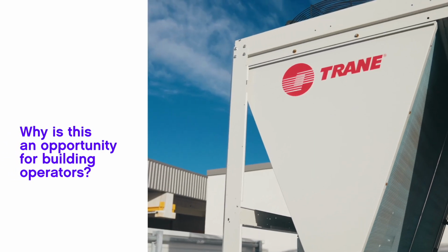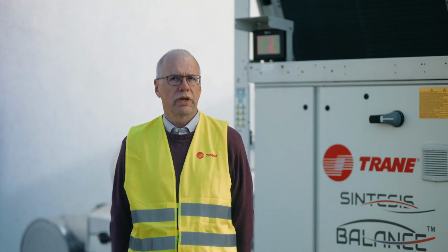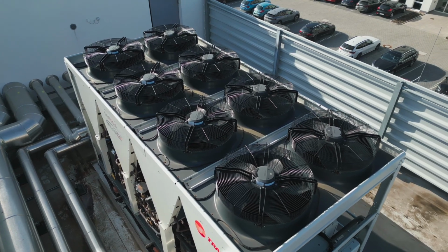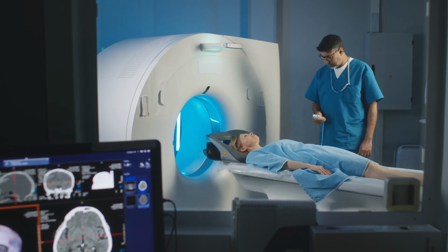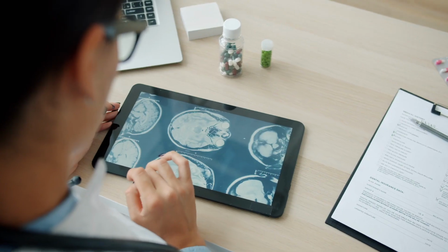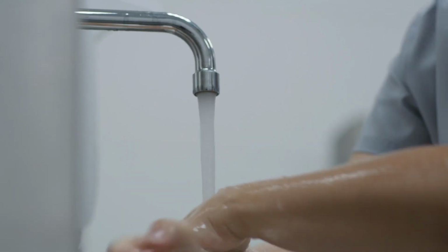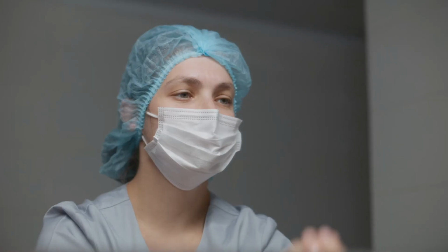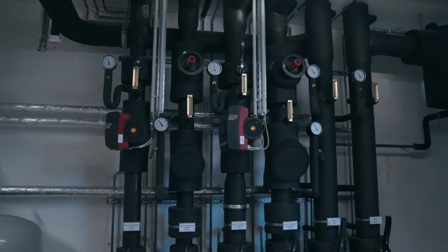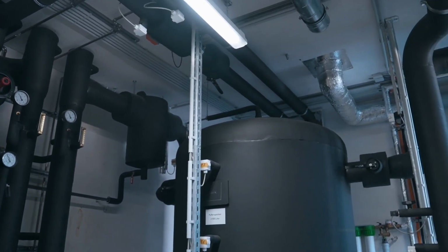Most buildings require heating and cooling. Simultaneous need depends really on the type of building, but you have buildings where you have a lot of potential for recovering the energy. For example, a hospital. In a hospital, you need cooling whatever the period of the year, and during the winter time, you need heating. The same in the summer: even if you don't heat the building itself, you need to produce sanitary hot water for the hospital. So there is a huge potential for recovering the heat from the cooling system for satisfying partially, or from time to time totally, the heating requirement of a building.